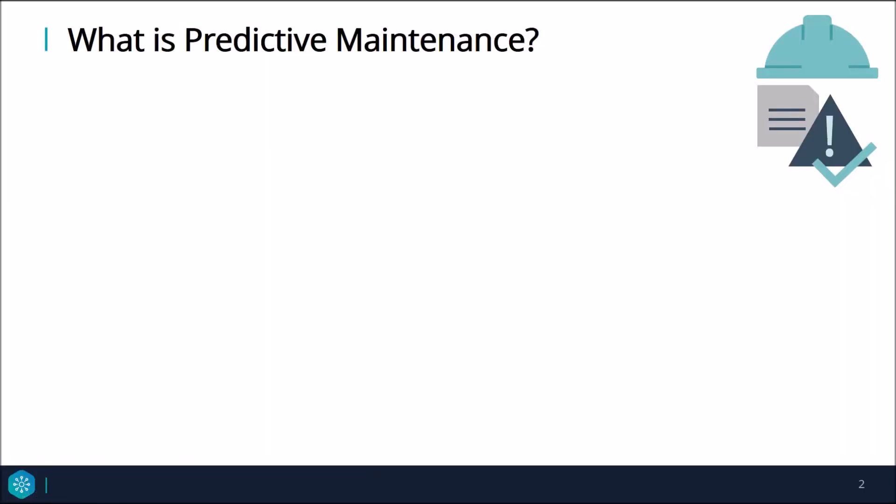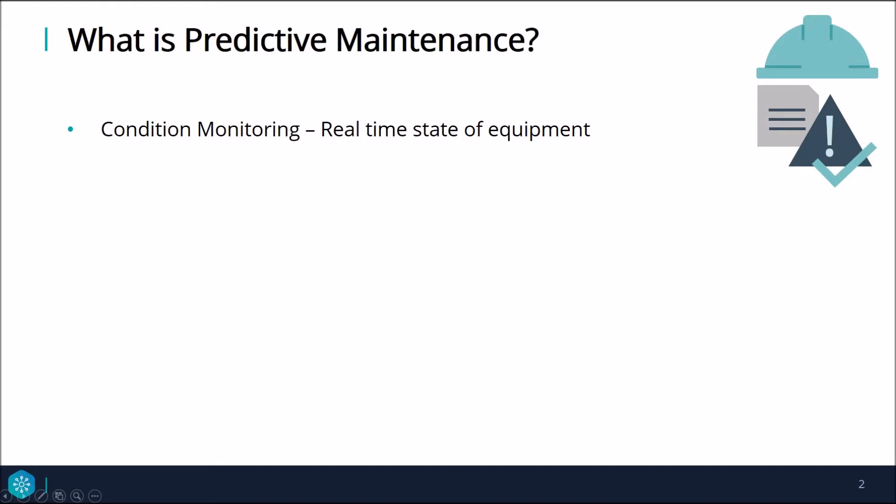First I'm going to define predictive maintenance by comparing it to other maintenance approaches and some of the shortfalls in each technique. Condition monitoring is the process of observing a parameter or condition in machinery, such as vibration or temperature, so that you can identify a significant change which may indicate a developing fault. Condition monitoring is used in predictive maintenance but does not predict a future failure or signal actionable events.